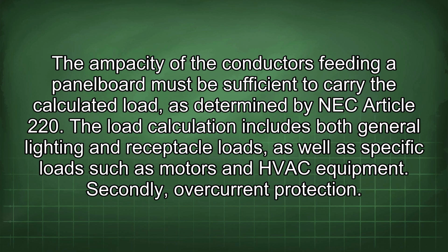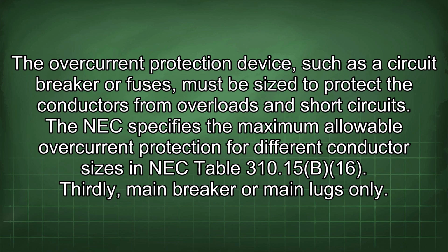Secondly, overcurrent protection. The overcurrent protection device, such as a circuit breaker or fuses, must be sized to protect the conductors from overloads and short circuits. The NEC specifies the maximum allowable overcurrent protection for different conductor sizes in NEC Table 310.15(B)(16). Thirdly, main breaker or main lugs only.